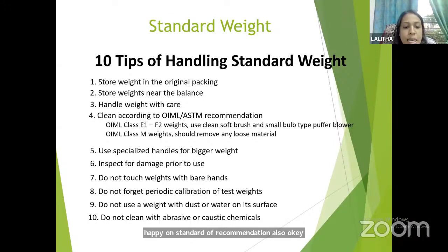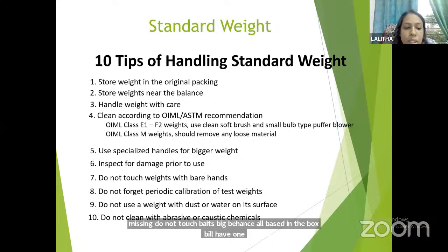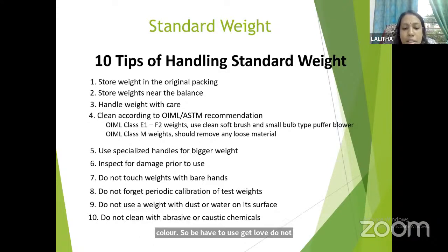Use specialized handles for bigger weights. Inspect for damage prior to use. Before using, check if there's any damage or any weight missing. Do not touch weights with bare hands. Always in the box we'll have one glove, so we have to use that glove. Do not forget periodic calibration of test weights. Do not use a weight with dust or water on its surface. Always make sure the surface is clean. Do not clean with other chemicals.